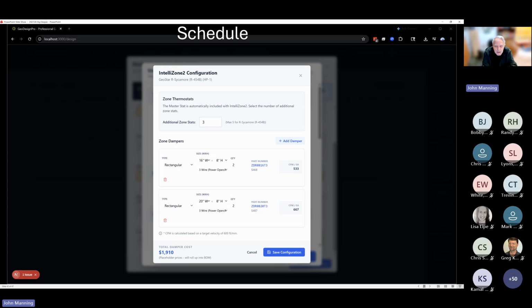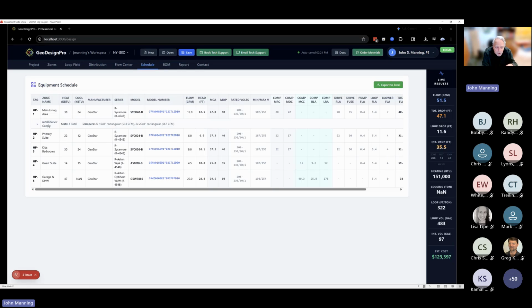You save the configuration. You do that for all 5 heat pumps, and the program will automatically populate the various electrical fields associated with that particular heat pump. So if you specified an IntelliStart, it'll look up the locked rotor amps that you're benefiting by installing an IntelliStart. You can export this schedule to an Excel spreadsheet where you can modify it to your heart's content.